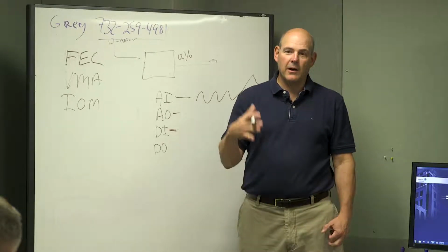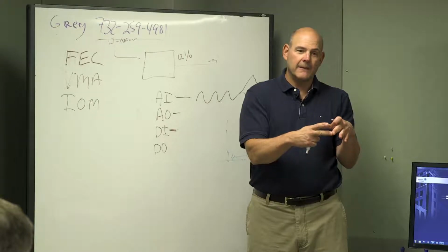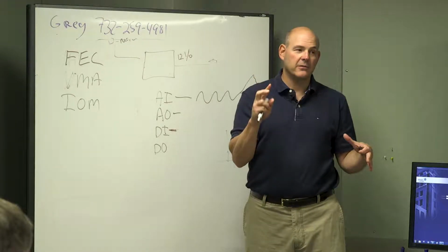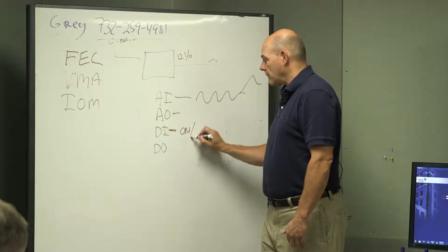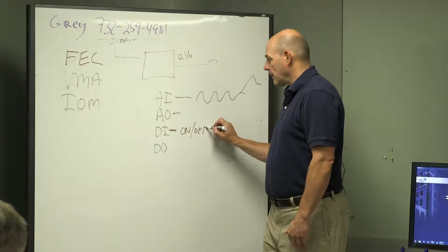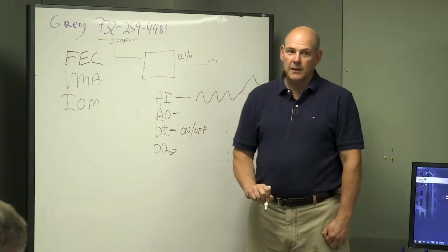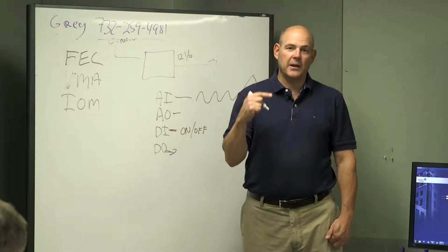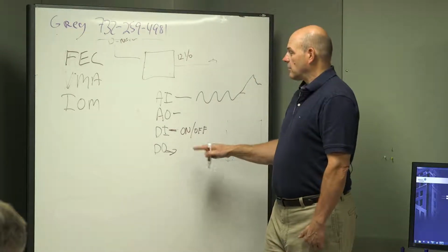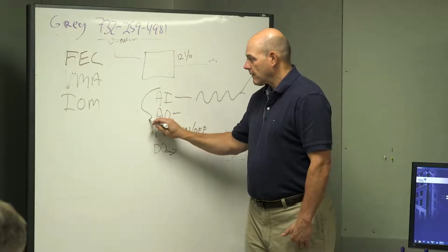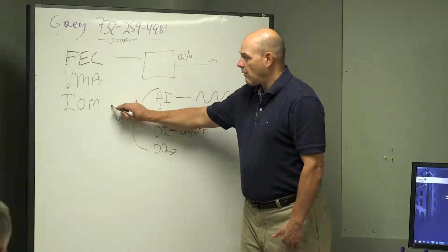So when you have a tower fan that comes on, there's a thing called a current donut. That sends a signal that the tower's on. So it's either on or off. So that's important to know. This is on or off. And the same thing with a digital output. It's on or it's off. So we're commanding a pump to come on or a pump to come off. So those are the 4 points that you need to know, and they're hardwired.